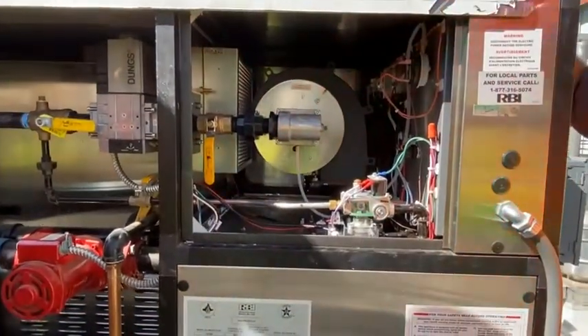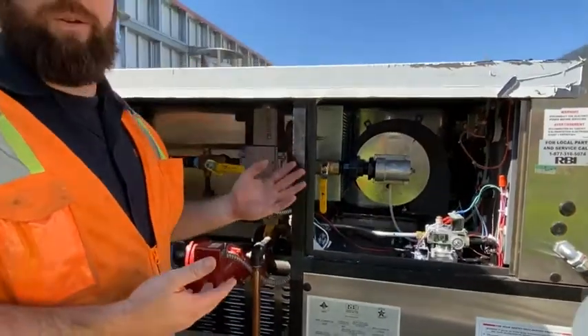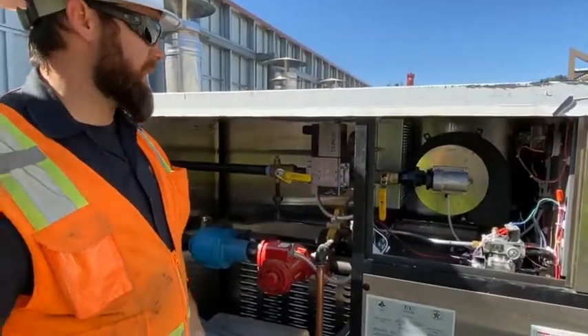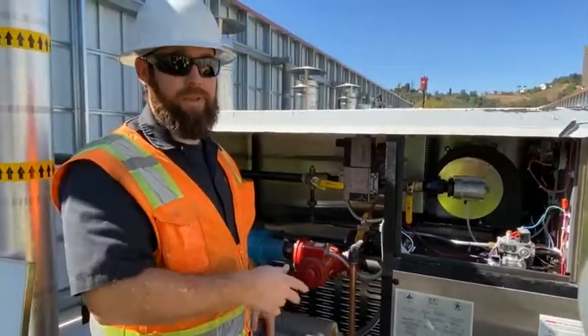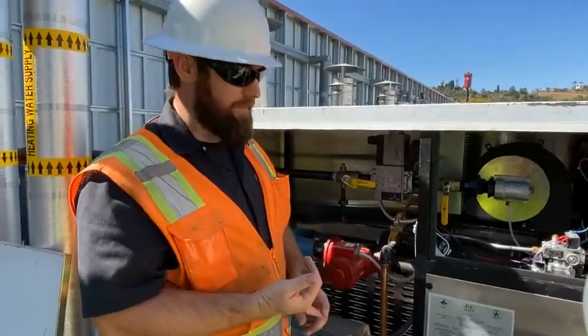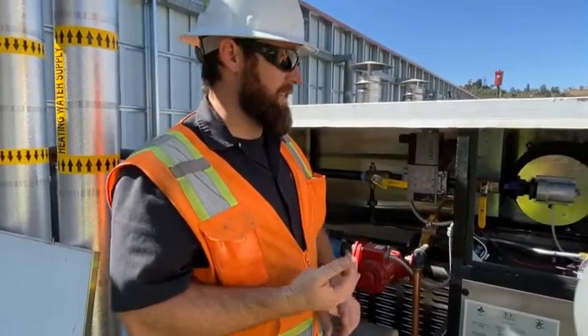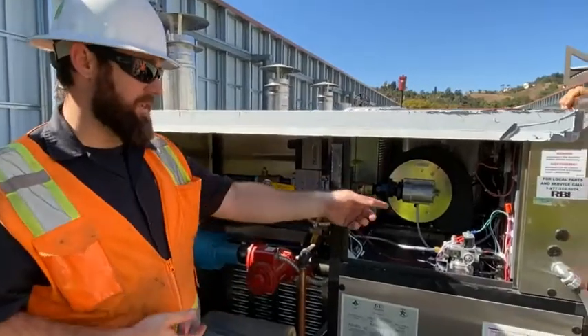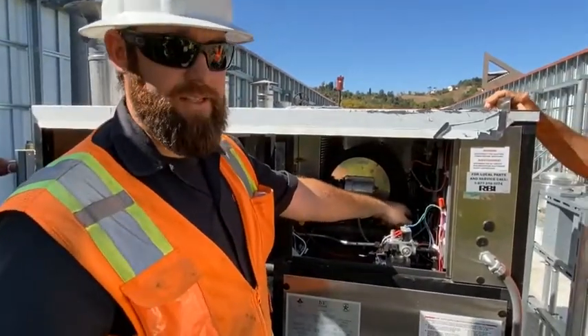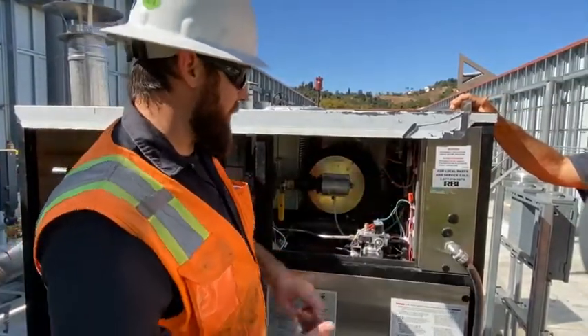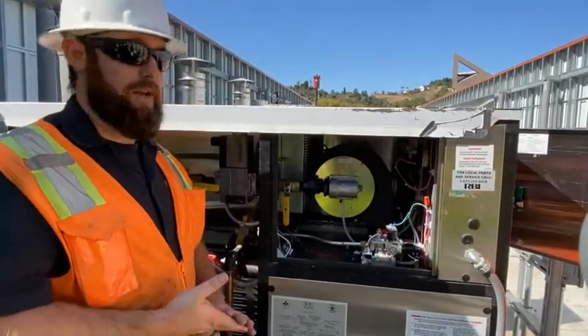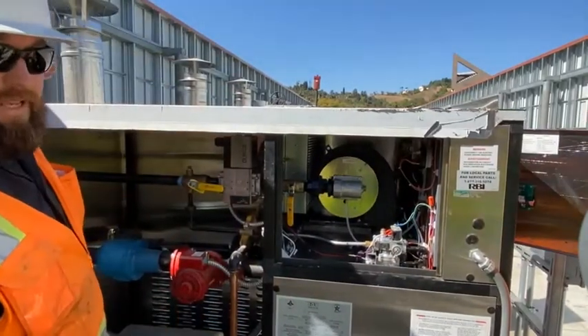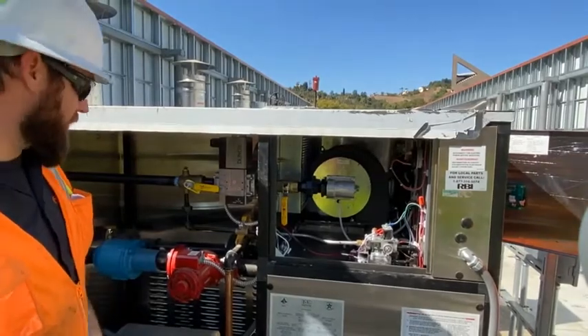And again, my company, we do annual maintenance on these all the time. So we completely open it up, clean everything out, replace filter, gaskets, igniters. We check the operation of the UV scanner, check the operation of the pilot, take pilot pressures. We do combustion analysis again on these, to make sure it's in the right running order.